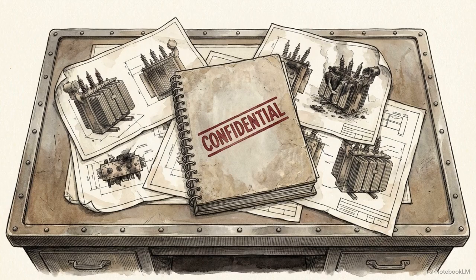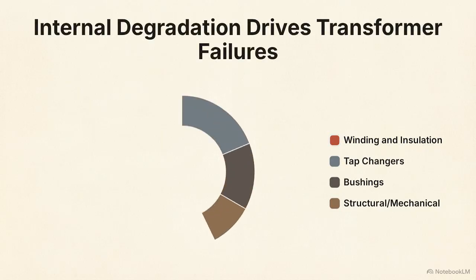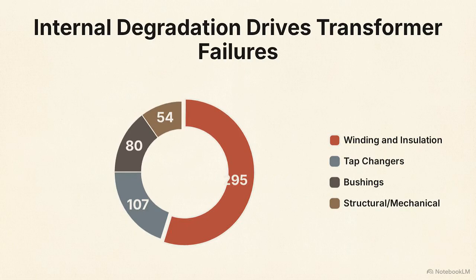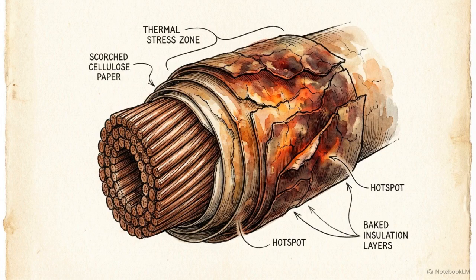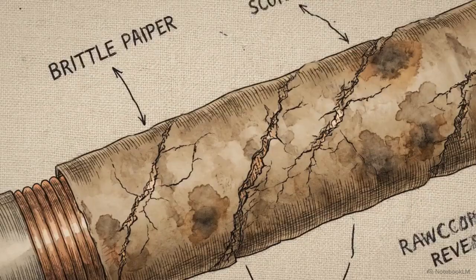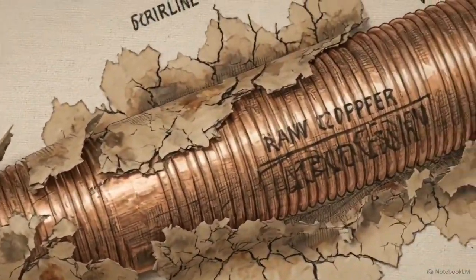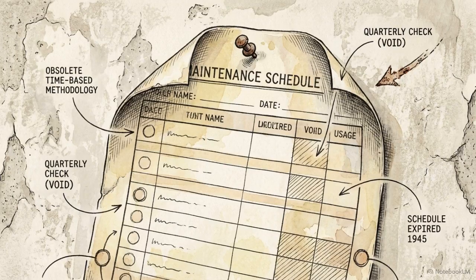To understand exactly how these assets die in the dark, we can look at an empirical analysis of 536 real-world transformer failures. This visualization breaks down those 536 failure cases. The dominant cause of death is not structural or mechanical. It is the degradation of the winding and insulation. Prolonged exposure to high temperatures bakes the internal insulation. This continuous thermal stress creates microfractures in the insulating material, compromising its dielectric strength and rapidly accelerating the timeline to a short circuit.